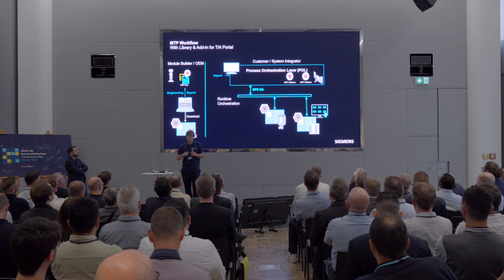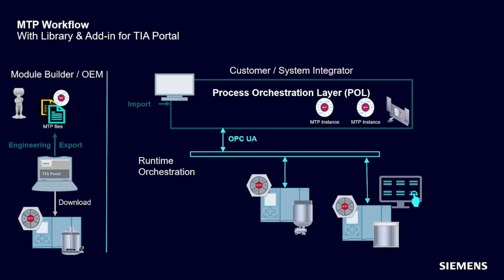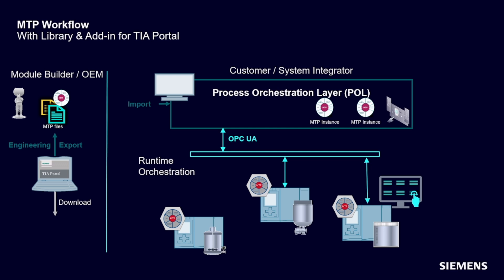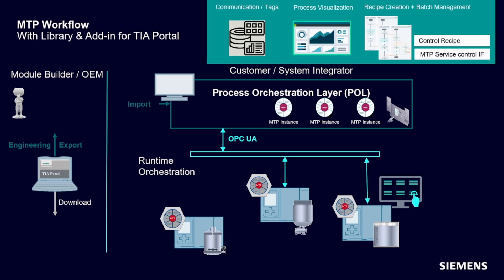What happens then? On the right-hand side we have the process orchestration layer — a SCADA system, DCS system, or MES system. The machine builders ship the machine to the plant and share the MTP file with the system integrator. Now the magic happens: with a few clicks, the SCADA system automatically generates the connection to the machine, the tags, the visualization, as well as the link to the batch and recipe system. You plug the machine to the network and are directly able to monitor and control it in the SCADA or DCS system.